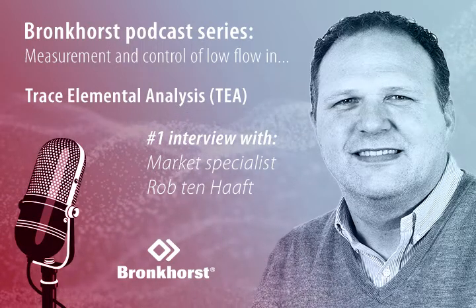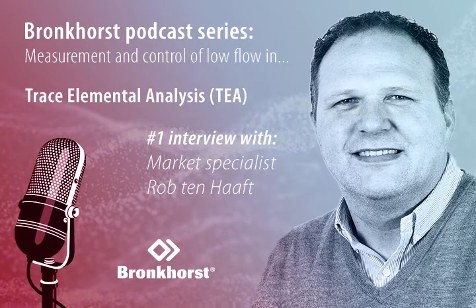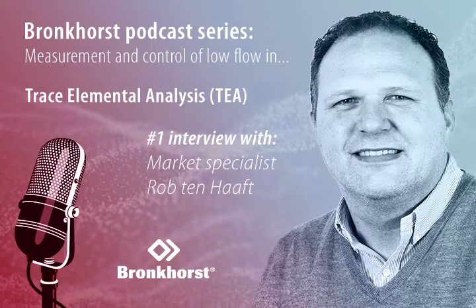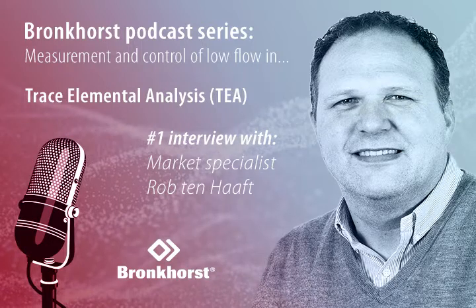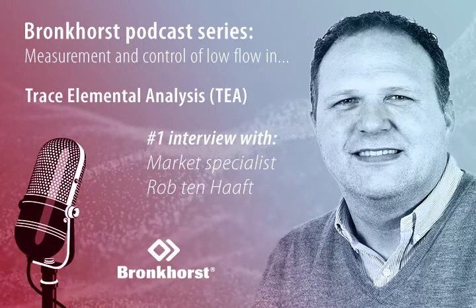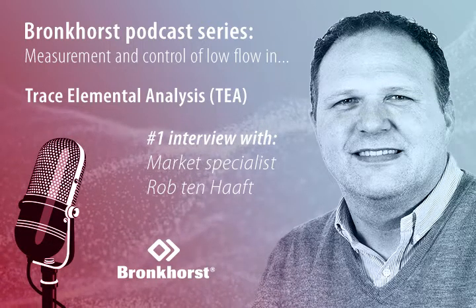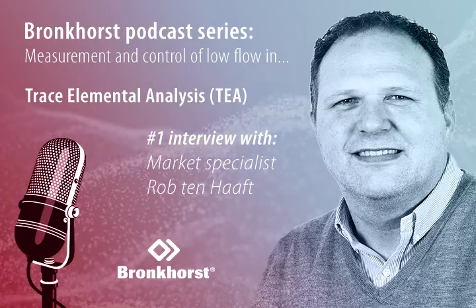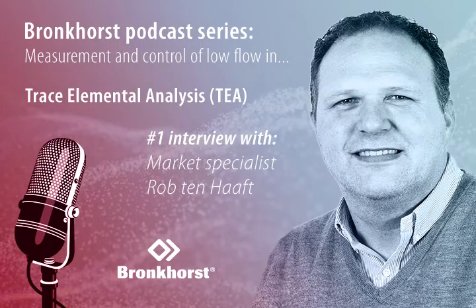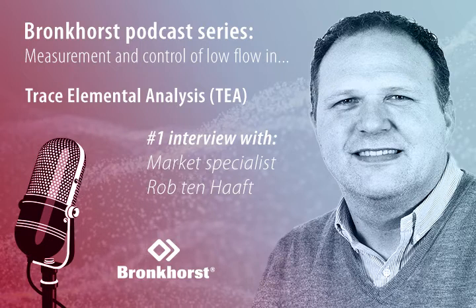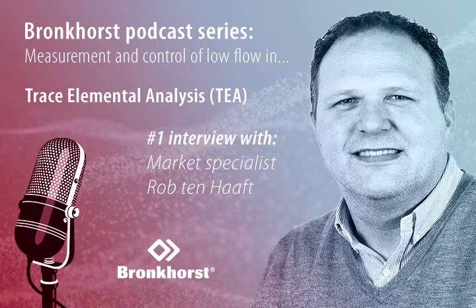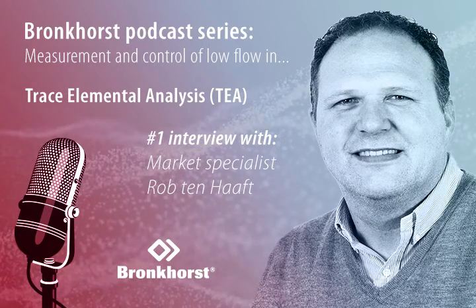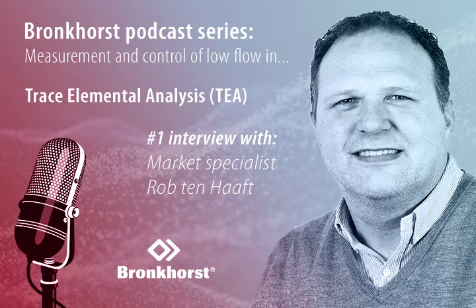And to mention mass flow, if you measure mass flow, and you know that, James, when you measure the mass, it is not influenced by outside parameters like temperature or pressure. So that's why Bronkhorst chooses mass, because it indicates repeatability, which you indicated earlier was a very important parameter. Correct. Yes.